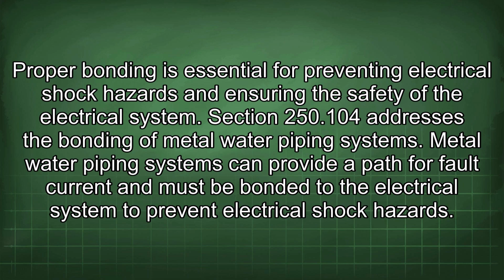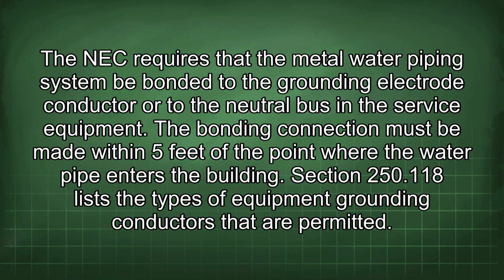Section 250.104 addresses the bonding of metal water piping systems. Metal water piping systems can provide a path for fault current and must be bonded to the electrical system to prevent electrical shock hazards. The NEC requires that the metal water piping system be bonded to the grounding electrode conductor or to the neutral bus in the service equipment. The bonding connection must be made within 5 feet of the point where the water pipe enters the building.